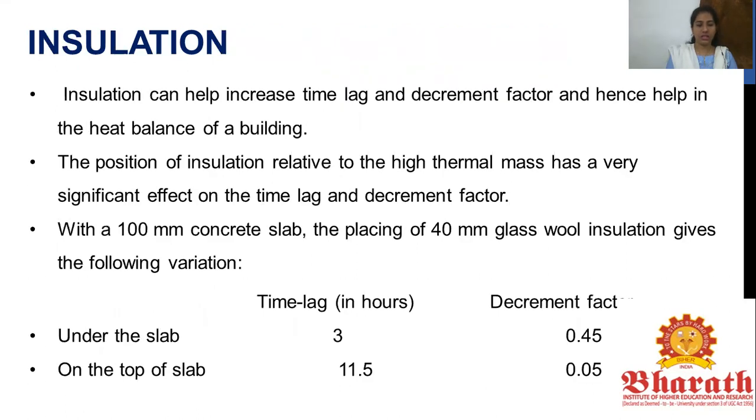So looking at what exactly insulation is. Insulation can help increase the time lag and the decrement factor, and this helps in the heat balance of a building. The position of insulation relative to the thermal mass has a very significant effect. It's talking about how where you place the insulation also plays a very important role.